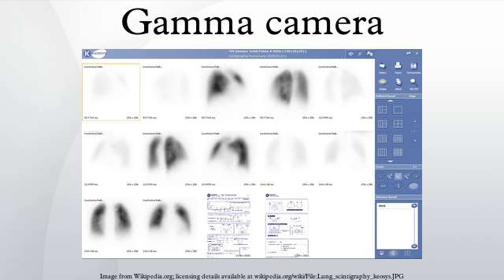After the flash of light is produced, it is detected. Photomultiplier tubes behind the crystal detect the fluorescent flashes and a computer sums the counts. The computer reconstructs and displays a two-dimensional image of the relative spatial count density on a monitor. This reconstructed image reflects the distribution and relative concentration of radioactive tracer elements present in the organs and tissues imaged.